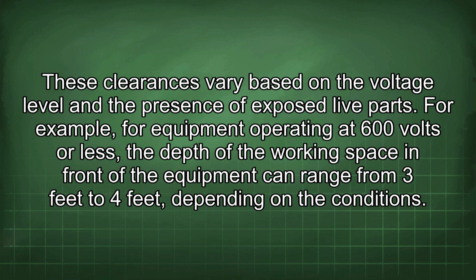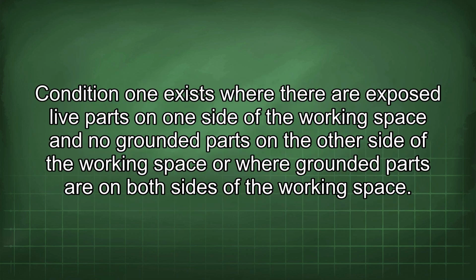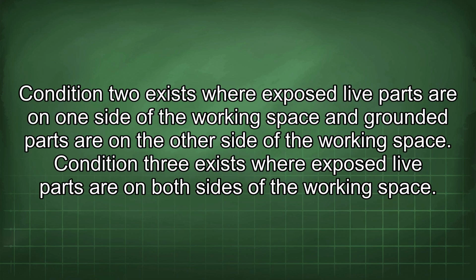For example, for equipment operating at 600 volts or less, the depth of the working space in front of the equipment can range from 3 feet to 4 feet, depending on the conditions. Condition 1 exists where there are exposed live parts on one side of the working space and no grounded parts on the other side of the working space, or where grounded parts are on both sides of the working space. Condition 2 exists where exposed live parts are on one side of the working space and grounded parts are on the other side of the working space. Condition 3 exists where exposed live parts are on both sides of the working space.